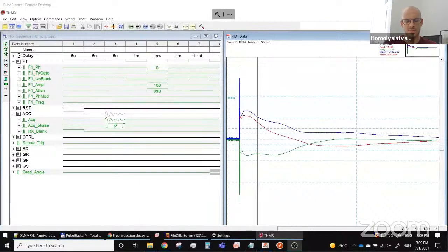Now let's take a look at a real NMR measurement. First of all, we apply a so-called 90-degree pulse. This pulse rotates the spins from the z-axis into the xy plane. After this, the spin directions rapidly lose their coherence, which is the so-called dephasing effect. The dephasing is due to the fact that each NMR magnet has an imperfect magnetic field that is not uniform. Therefore, each nucleus spins with a little bit different frequency. The observed NMR signal is known as a free induction decay or FID.